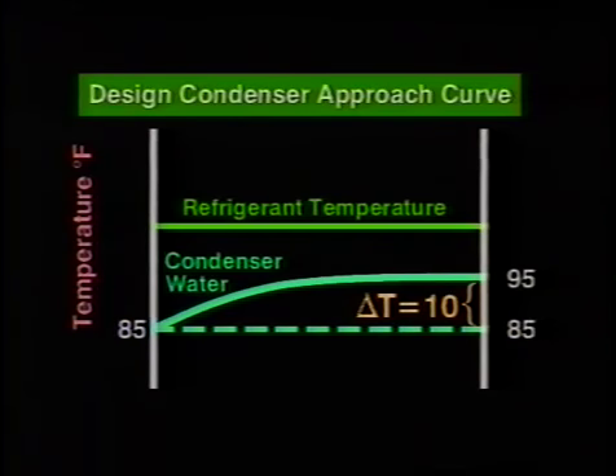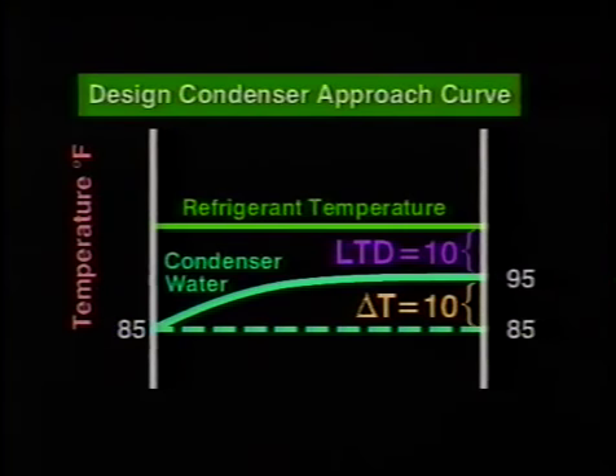The refrigerant saturated condensing temperature will normally run 6 to 12 degrees above the leaving water temperature, with 10 degrees being typical. So we would expect these conditions to give us about 105 degrees Fahrenheit saturated condensing temperature. And again, we need to remember that this is for full load conditions.